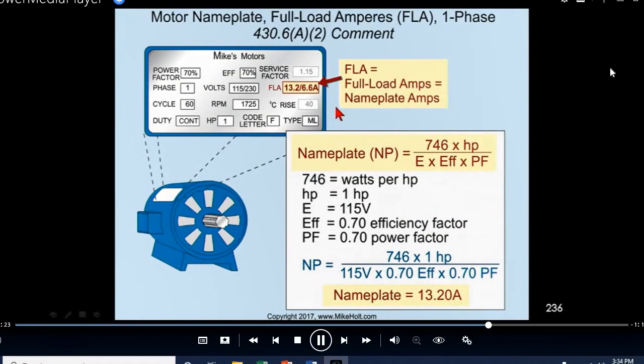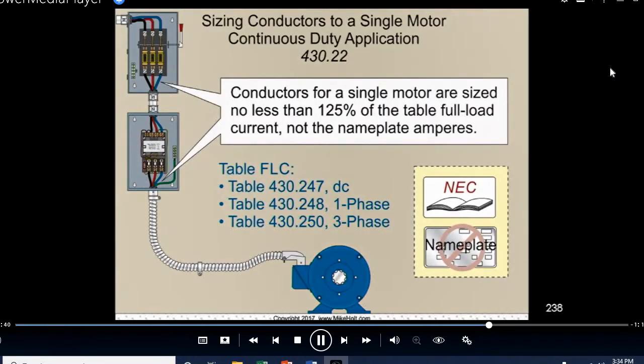Here's an example of a nameplate. The nameplate is calculated out with a function of this formula, having to know voltage, efficiency, and power factor, and we will never be using the nameplate for sizing the conductors and the protection device for short circuit and ground fault protection. Single motor. How do you size the wire to a single motor? Well, the code says the conductors for a single motor are sized no less than 125% of the table full load current, not the nameplate value. And you go to the different tables and you look them up, and the table will give you a value.